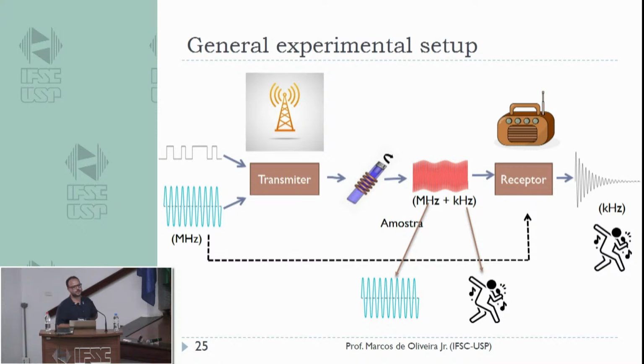So what we have in the spectrometer, that's sending the signal to the probe and getting it back also from the probe, is a transmitter that's putting together our pulses in the right frequency. They send this signal to the sample, so I put here an antenna to represent this radiation. The sample is irradiated, and it has a response.